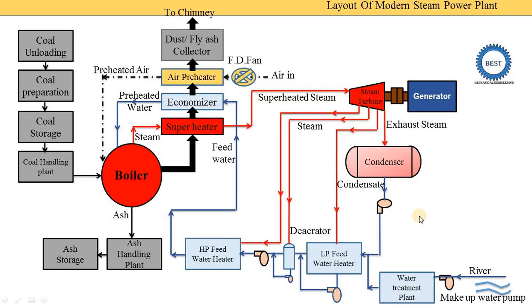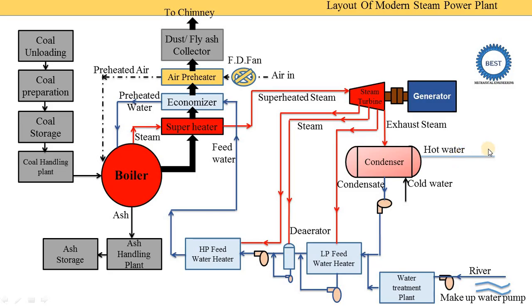The fourth circuit is the cooling water circuit. In the condenser, steam is converted into water, and for this we need to supply cooling water. Cold water is supplied to the condenser and absorbs heat energy from the steam, becoming hot water. For the cooling circuit, there are two options: an open system or a closed system. In the open system, water is taken from a river, supplied to the condenser, and the hot water coming out is returned to the river. In areas where water is available in limited quantity, a closed circuit using a cooling tower is used.